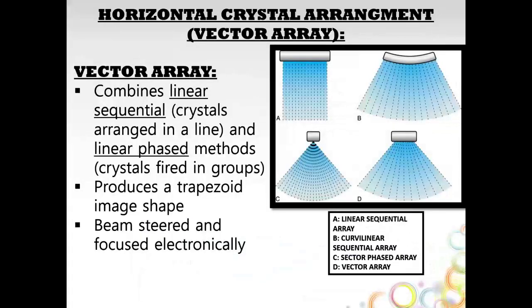You also have vector arrays. So vector arrays combine the linear sequential technology, where crystals are arranged in a line, but they also combine the linear phasing technology, the same phasing technology that a sector array transducer has, where the crystals are fired in groups. By combining both of those things, similar to the sector transducer we were talking about just a minute ago, it produces a trapezoid image shape, or triangular shape, some people call it. And this beam is steered electronically and focused electronically.